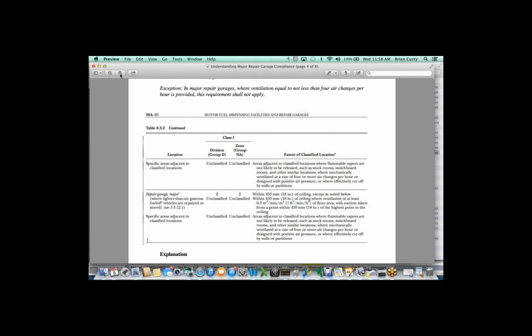So we've never touched the electrical at any ceiling. We've always opted to put emergency exhaust in, which really, from a practical approach, if you think about it, and I've been in shops multiple times where the tank contents have released, that's where the gas goes. That's the area you want to release. That's the area you want to ventilate. And as long as you're doing that, you've met the ventilation requirements and you've met the electrical classification requirements. And it's a lot cheaper, depending on how old the building is, to add ventilation than it is to gut the ceiling and remove all the electrical that's up there. So that was more or less our approach.